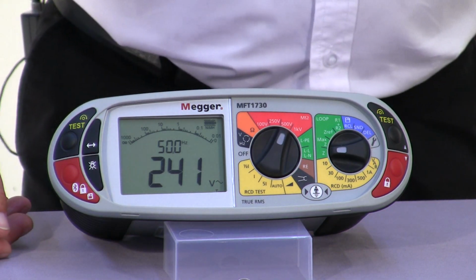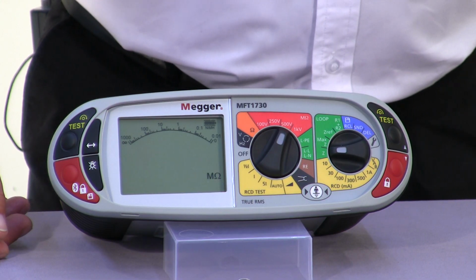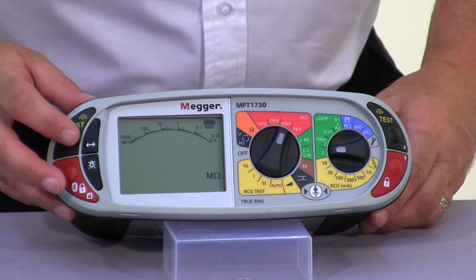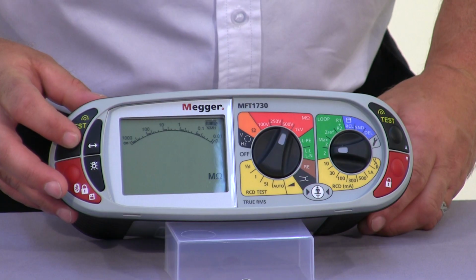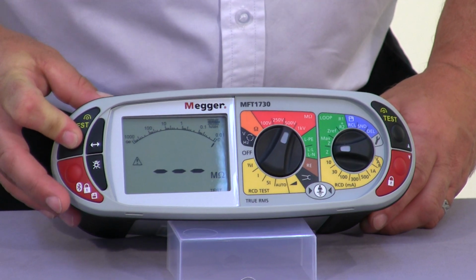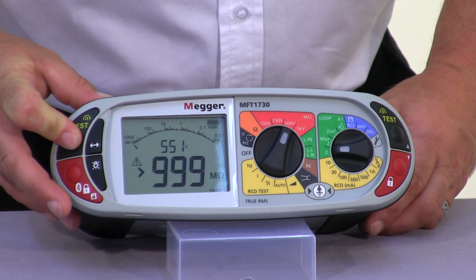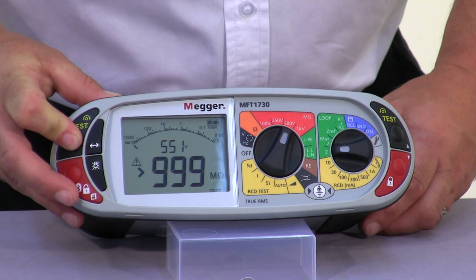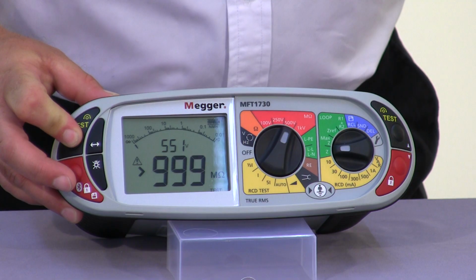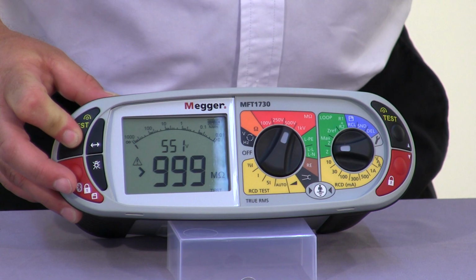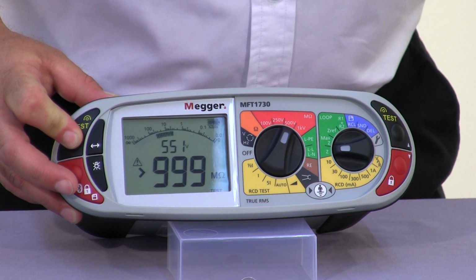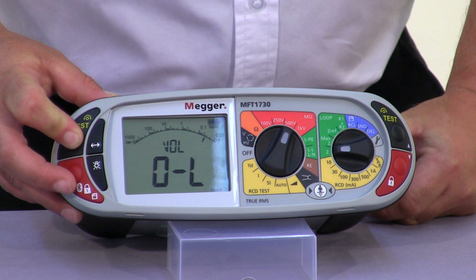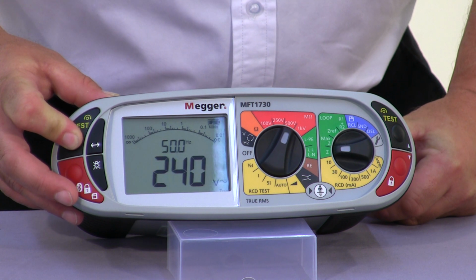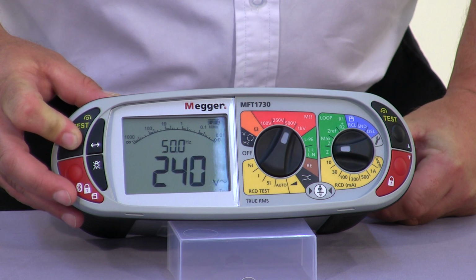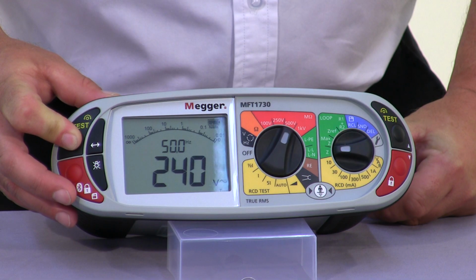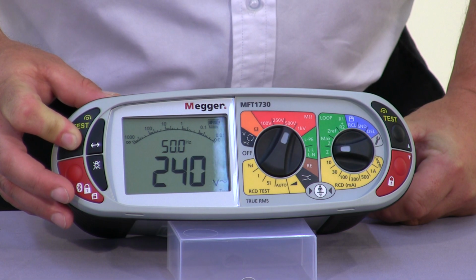So again, we apply the probes to a mains voltage, and as you can see, indication on the screen incorporating the frequency as well. Now this input protection is extended now to be incorporated even when we're actually carrying out a test. So for example, it's a 500 volt insulation test. You can see we've got an output of 551 volts. If accidentally applying the mains voltage, you'll see again audible indication, it's indicated on the screen, and now it's displaying the voltage that we've attached the probes to.